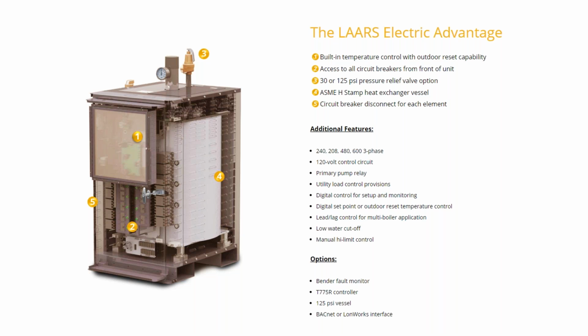One of the other benefits is that there is a circuit breaker for each element, so you can swap these things in and out relatively easily and safely. There's a 120 volt control circuit, so the controls are very easy, and there's a primary pump relay built right in. So this is really a great product that can be integrated into a BACnet or LonWorks interface. And in that situation where maybe you've moved over to a VRF or something, and you need something to heat up the space a little bit more than what that can handle, this will step right in and do the job with minimal modifications.